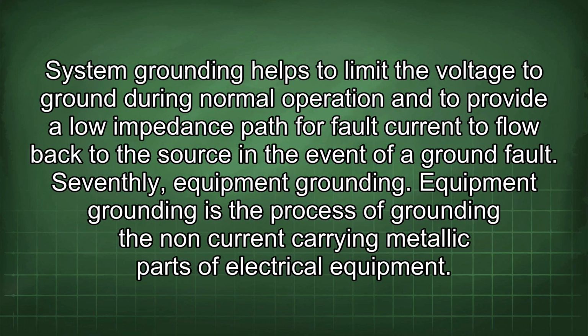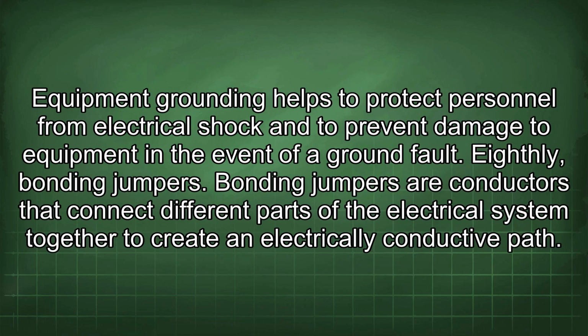System grounding helps to limit the voltage to ground during normal operation and to provide a low impedance path for fault current to flow back to the source in the event of a ground fault. Seventhly, equipment grounding. Equipment grounding is the process of grounding the non-current carrying metallic parts of electrical equipment. Equipment grounding helps to protect personnel from electrical shock and to prevent damage to equipment in the event of a ground fault.